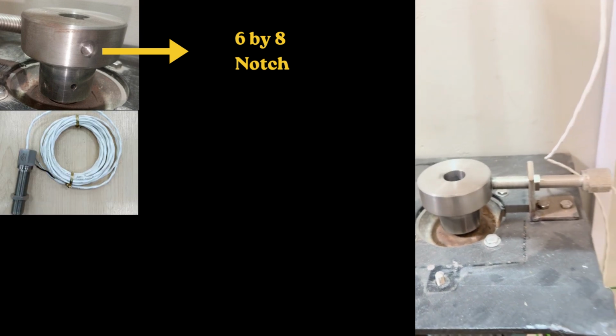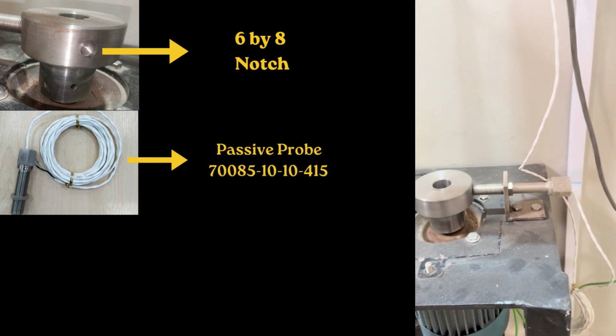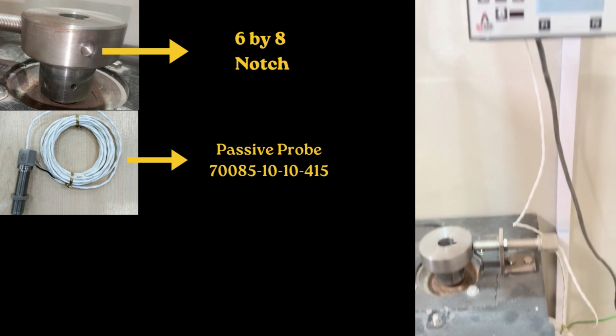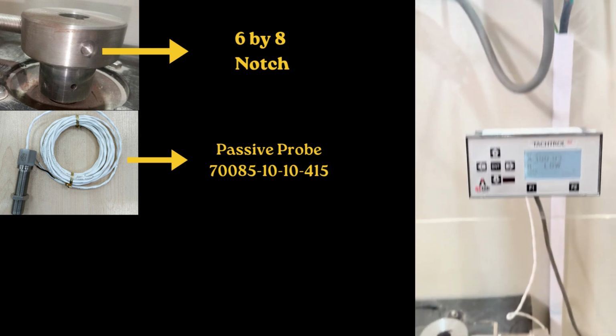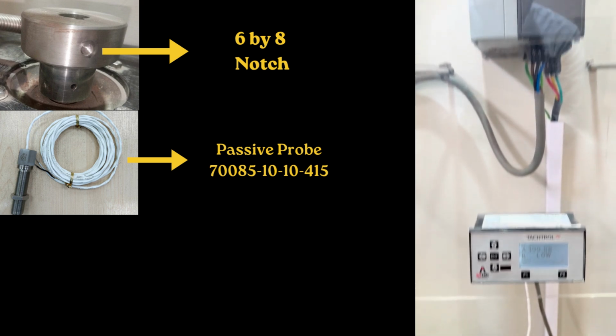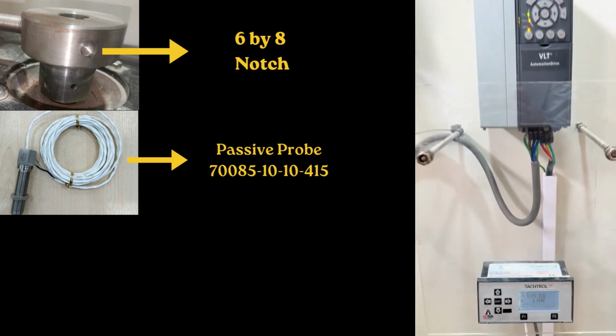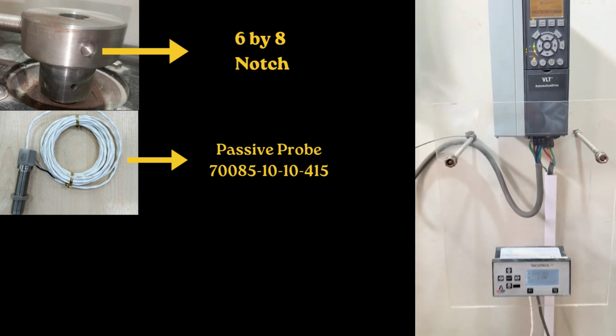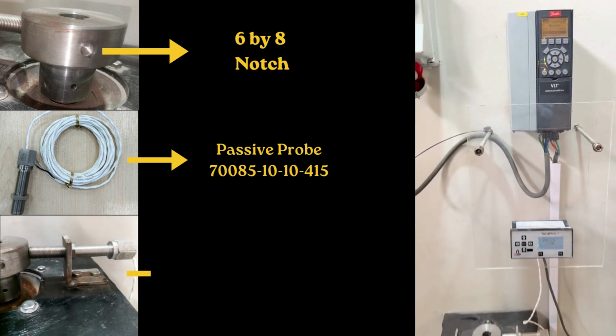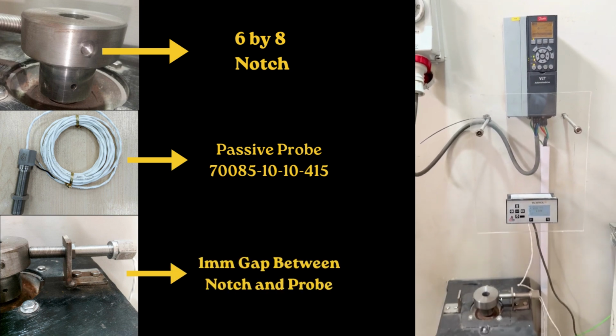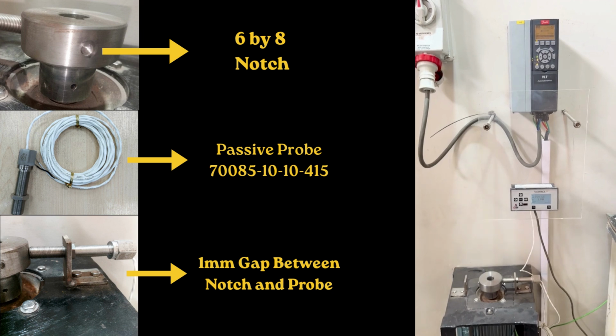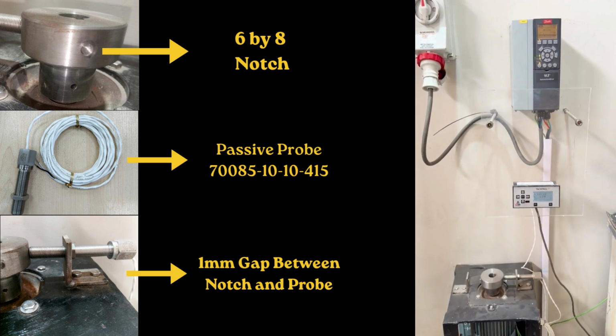The speed probe used in this setup is a passive magnetic pickup sensor. As the notch passes in front of the probe, the changing magnetic field induces electrical pulses in the sensor. The probe is installed at an approximate gap of 1 mm from the coupling, which ensures proper signal generation and accurate detection.